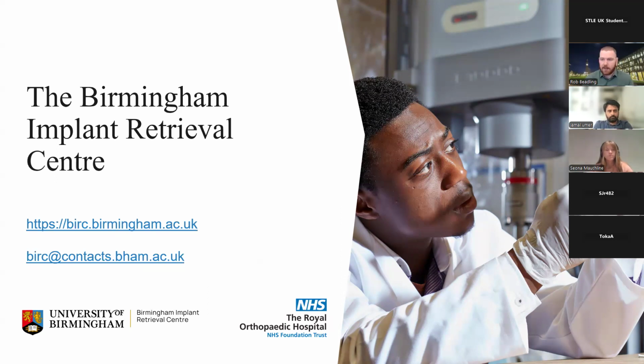One of the key things that we're seeing right off the bat is devices that come out after 15 years, say, which you would consider a success. It's lasted for 15 years, it's restored function to the patient for a long period of time, it's a well-performing device, but it's failed for whatever reason. They come out looking mangled. They come out destroyed, articulating on all kinds of different areas, and it reinforces that message that how we test these things preclinically in no way represents the scenarios that they undergo in vivo. So we need to do better in terms of that preclinical assessment.